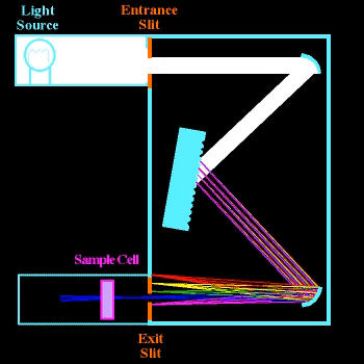When these light bands arrive at the exit slit, they form closely spaced individual colored bands grouped by wavelength. If you could look at the back of the exit slit, you would see a rainbow of light shaped like the entrance slit. As our movie shows, all red light rays converge on one spot near the exit slit, all greens at another, all blues at a third, and so on.